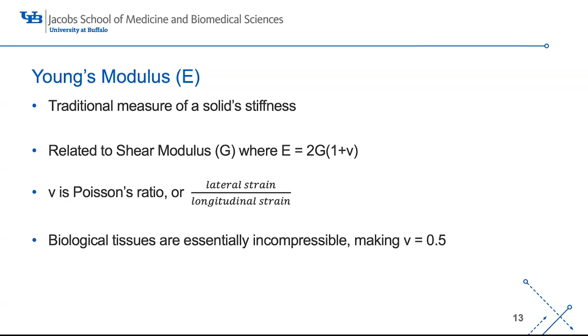Other elastography techniques, I'll touch mostly on stress or compression elastography. And that's because this is what Jonathan Ophir created when he pioneered the technology of elastography. What this does is, rather than using a shear wave to generate a shear force against tissue, you, the operator, are creating that force by just pressing the transducer onto tissue. And from that, you get an idea of the strain you're putting on tissue. So you can take a before and after B mode image, and from that you can get a color map elastogram to demonstrate the stiffness of the tissue you're looking at. You can see here the pictorial, like pre and post compression, and the stress you're putting on the tissue.